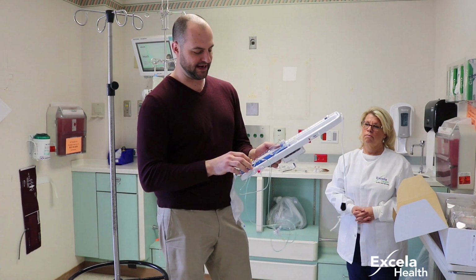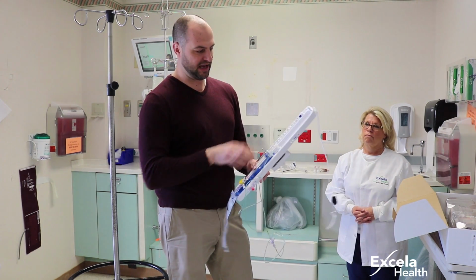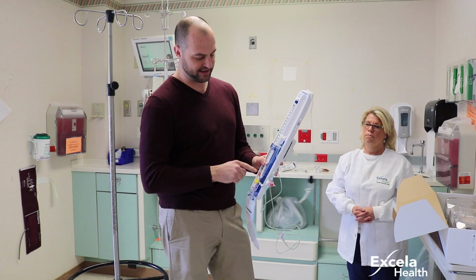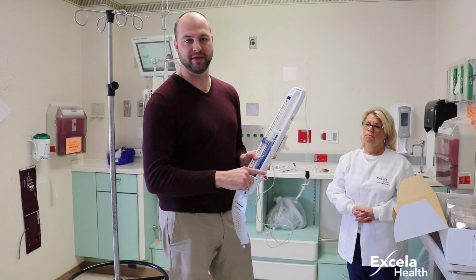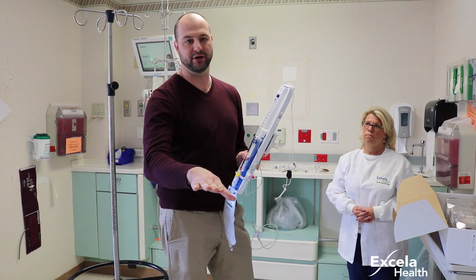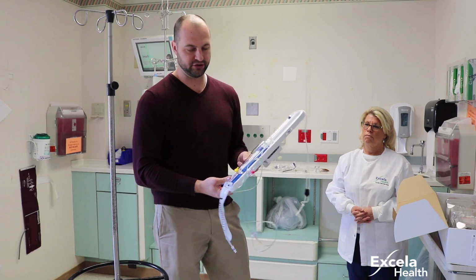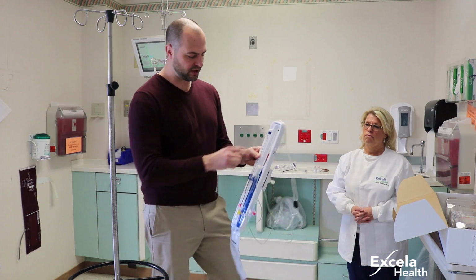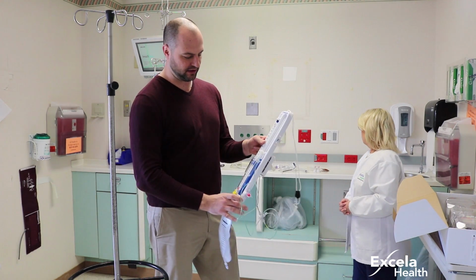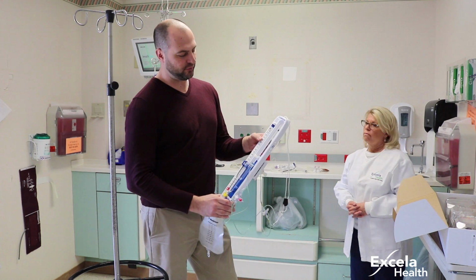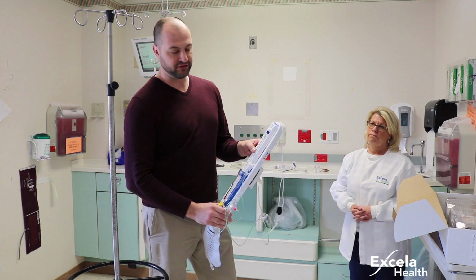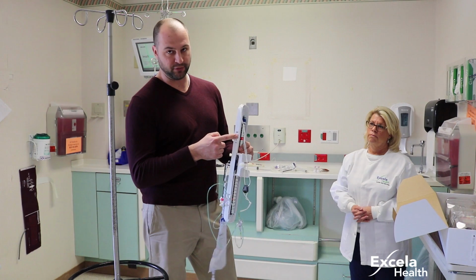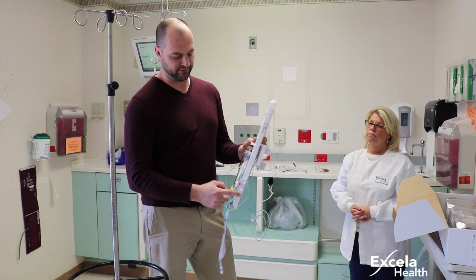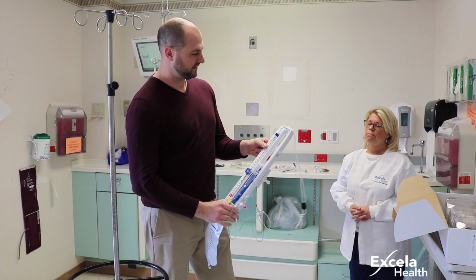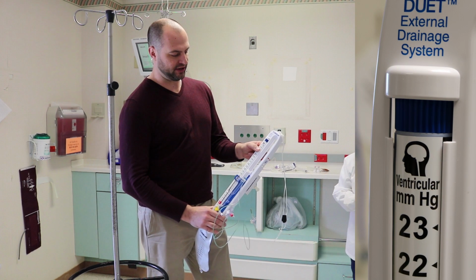So that when this is set up for the patient, and we have this set up for ventricular on the scale, the 0 is lined up with the main system stopcock, which is lined up with where the patient's insertion is. One of the important notes about the scale on this device is that you have 4 different options. You have ventricular and you have lumbar. Remember, we had the lumbar part up here if you were measuring lumbar; now we're doing ventricular. So you want to make sure that you have it on the ventricular side.